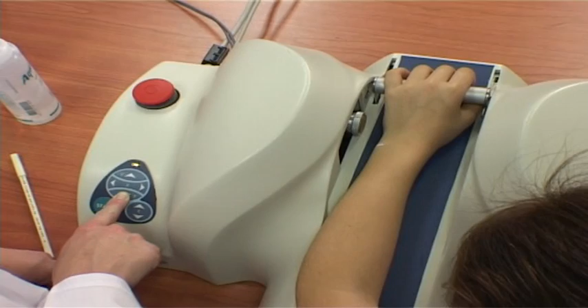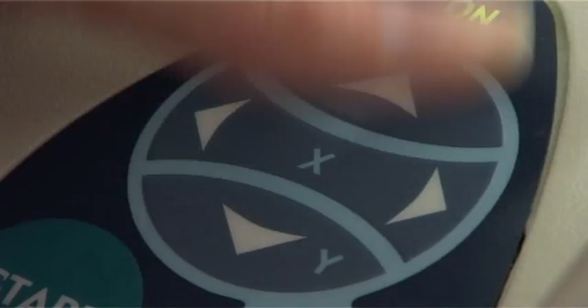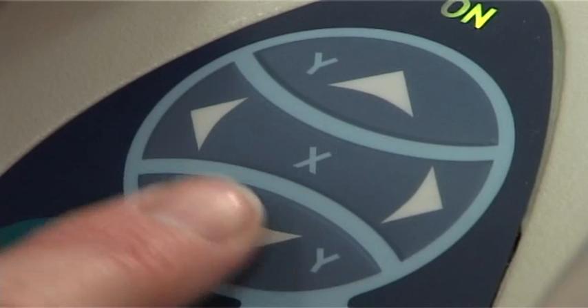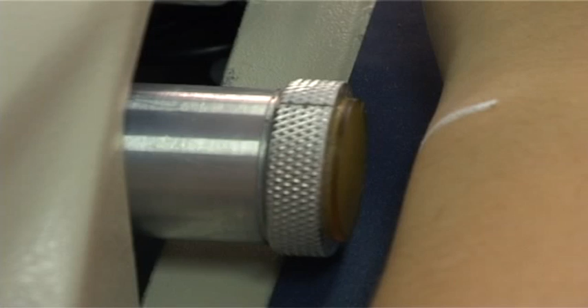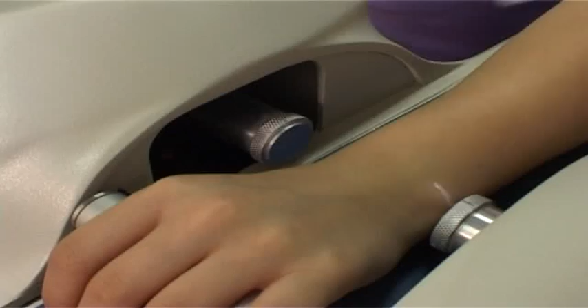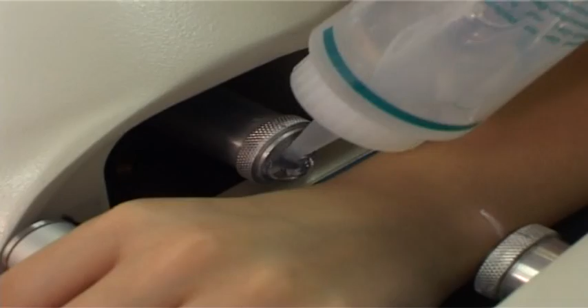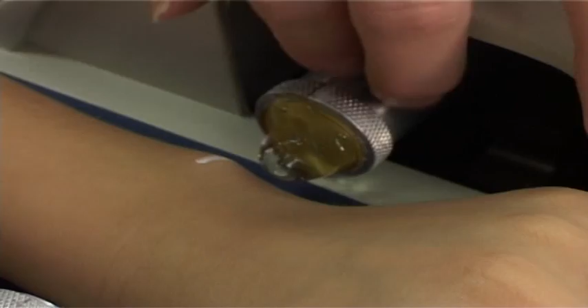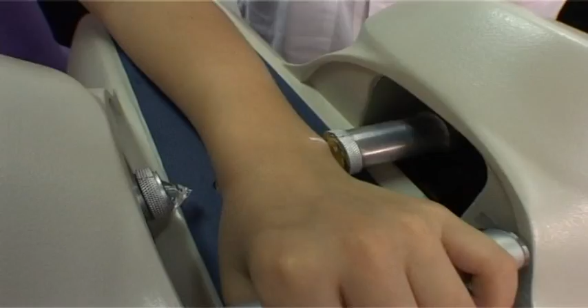The operator now adjusts the position of the transducers to the patient's arm. She presses the XY switches on the measurement unit, or the movement buttons on the measurement screen, until the midline, marked on the top of each transducer, is precisely aligned with the vertical line of the skin mark. Next, the operator applies gel to the two transducer heads. Now, the measurement is ready to start.